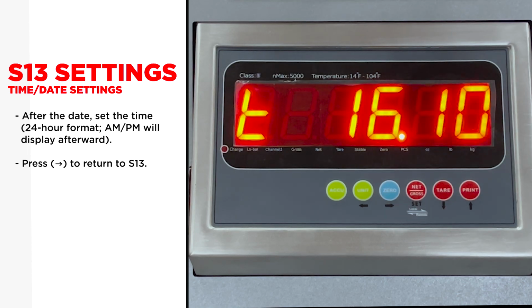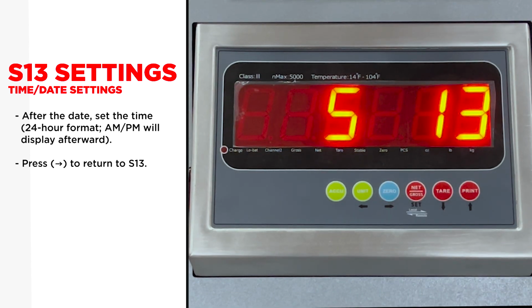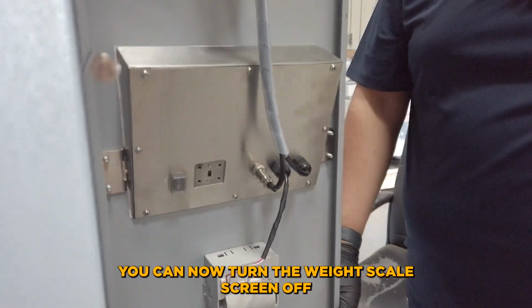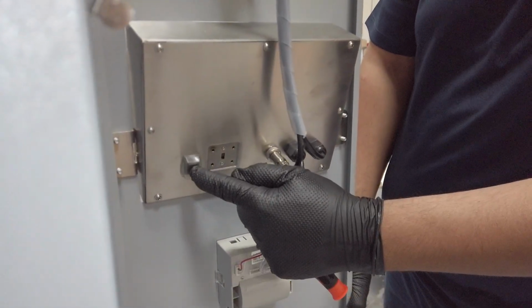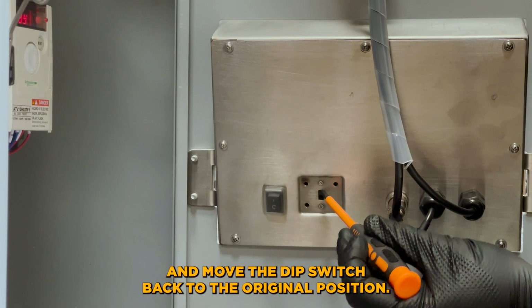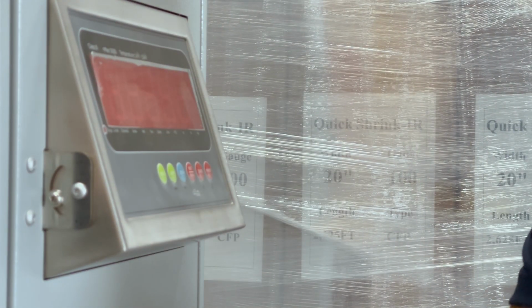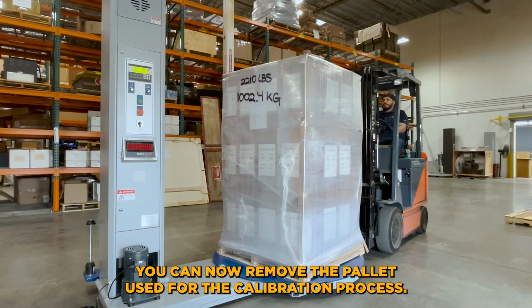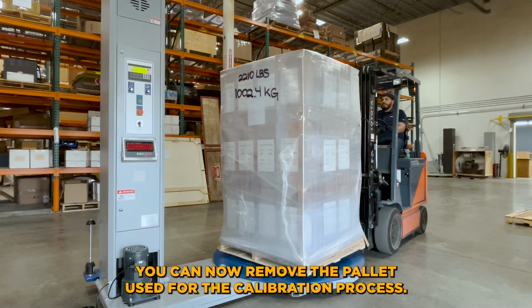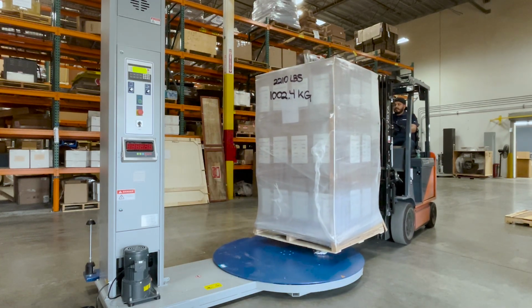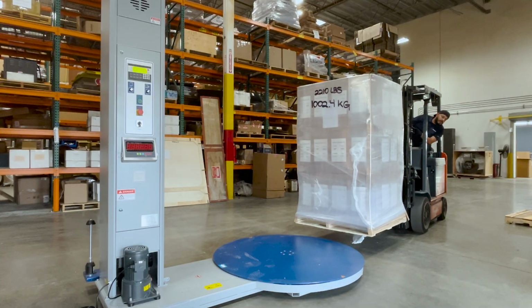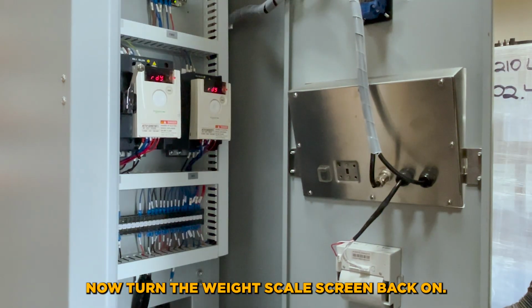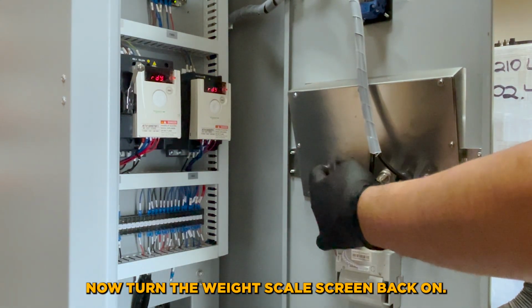Now press the right arrow. Now it shows S13. You can now turn the weight scale screen off and move the dip switch back to the original position. You can now remove the pallet used for the calibration process. Now turn the weight scale screen back on.